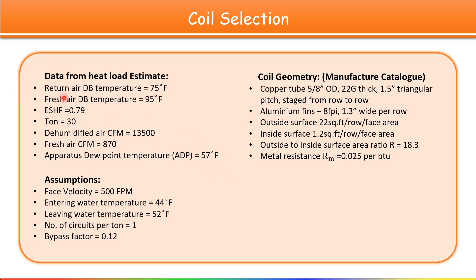Now some assumptions are also required. As per thumb rule, face velocity should always be less than or equal to 500 FPM. The chilled water entering temperature we have considered is 44°F, and chilled water leaving temperature is 52°F.